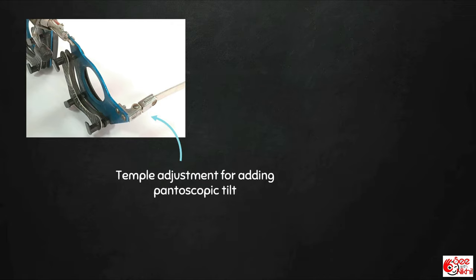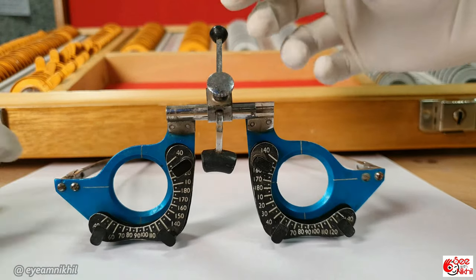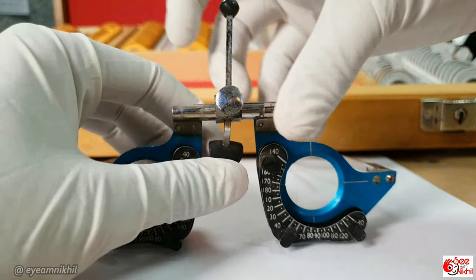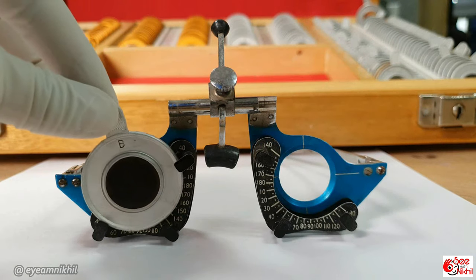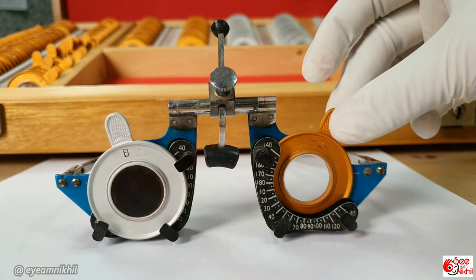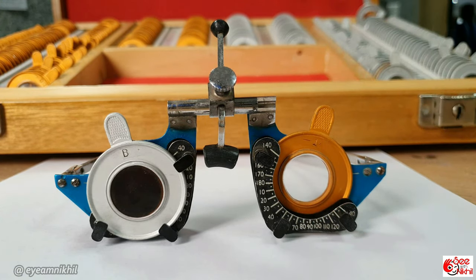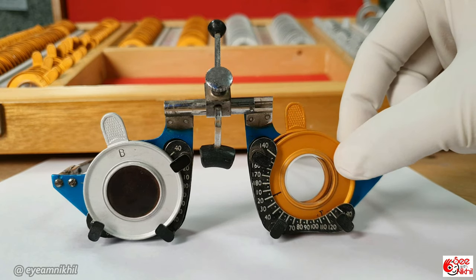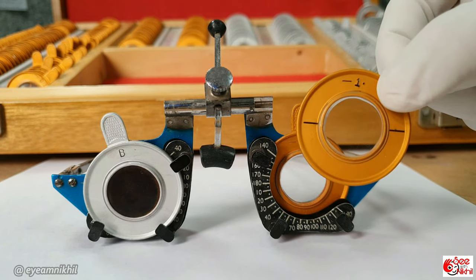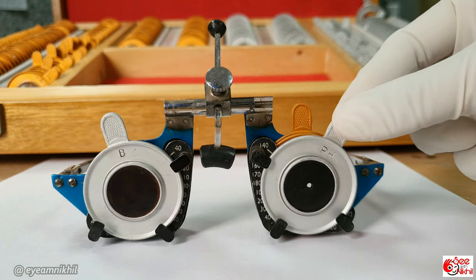Temple adjustment can be done for adding pantoscopic tilt to the frame, to make it similar to the actual frame the patient will wear. Pantoscopic tilt is the amount by which the frame is tilted with respect to the plane of the face. By rotating the knob, both the nose rest and IPD can be adjusted. When testing one eye, the other eye is occluded using an occluder. Spherical lenses are placed in the second compartment and, having a handle, cannot be rotated completely — nor is rotation needed as their power is uniform throughout. Cylindrical lenses are placed in the third compartment where markings are present and can be rotated 360 degrees to bring the axis to the desired marking. Accessory lenses can be placed in the anterior-most compartment.